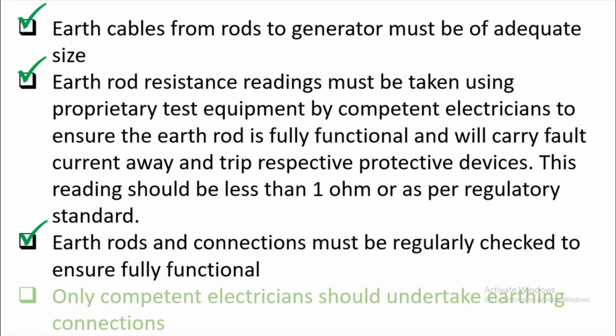So it's not only that you install it and then after six months you come back to check it. No, it's not. We should have a periodic schedule of inspection for all the earth rod connections. So this is the job of your competent electricians to make sure that this will happen, inspected periodically, and all inspections should be recorded on the appropriate forms that your company provided.